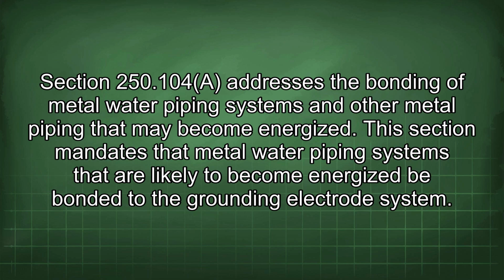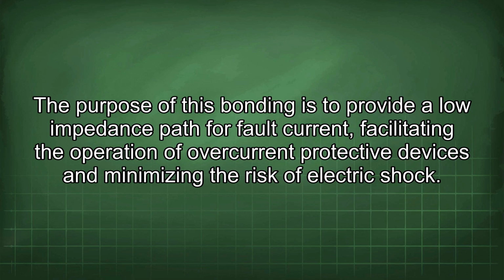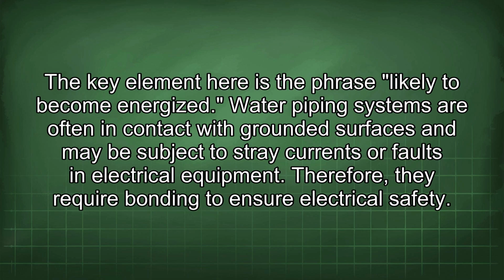250.104 addresses the bonding of metal water piping systems and other metal piping that may become energized. This section mandates that metal water piping systems that are likely to become energized be bonded to the grounding electrode system. The purpose of this bonding is to provide a low impedance path for fault current, facilitating the operation of overcurrent protective devices and minimizing the risk of electric shock. The key element here is the phrase "likely to become energized." Water piping systems are often in contact with grounded surfaces and may be subject to stray currents or faults in electrical equipment. Therefore, they require bonding to ensure electrical safety.